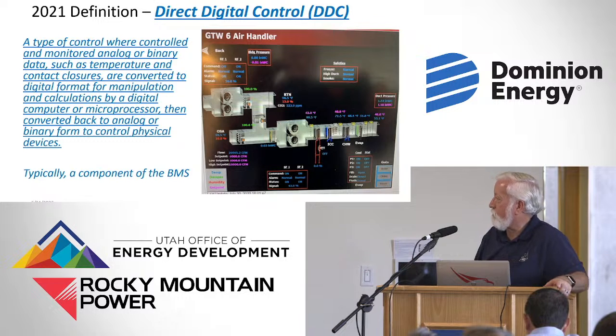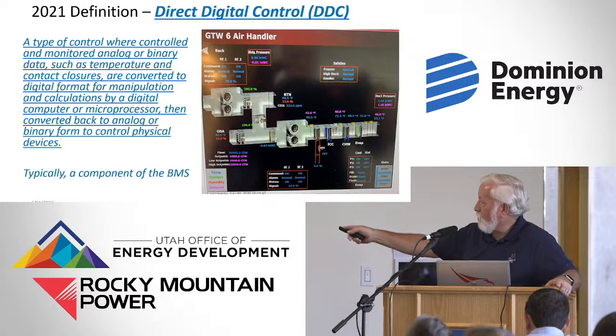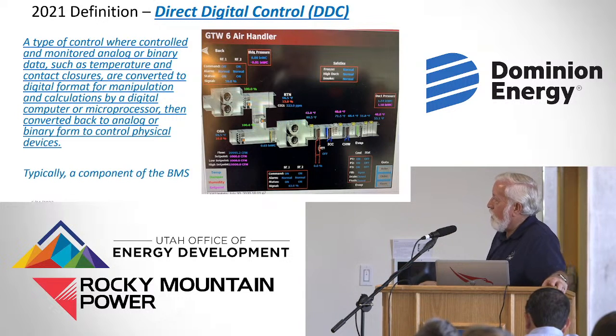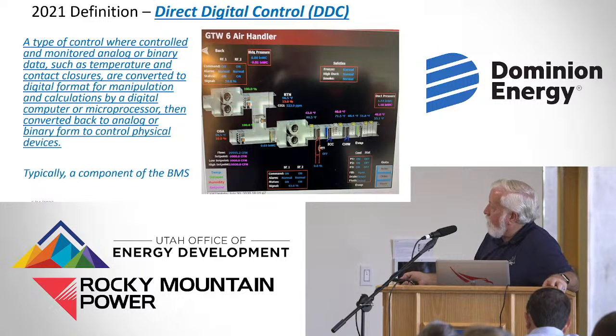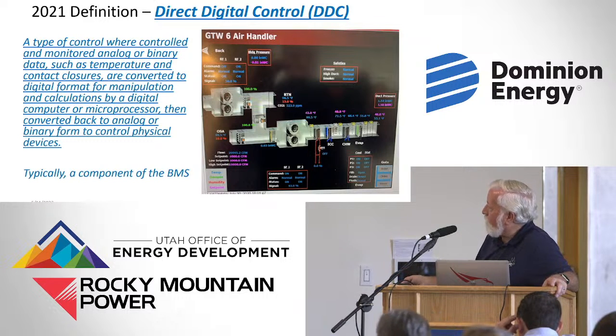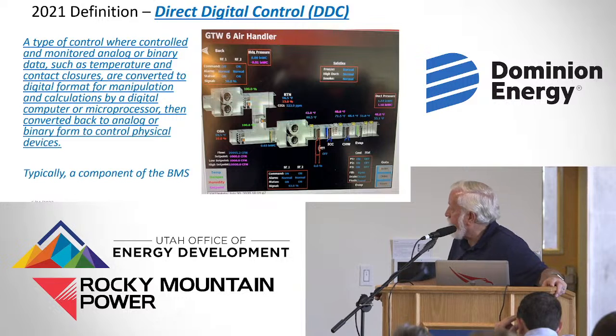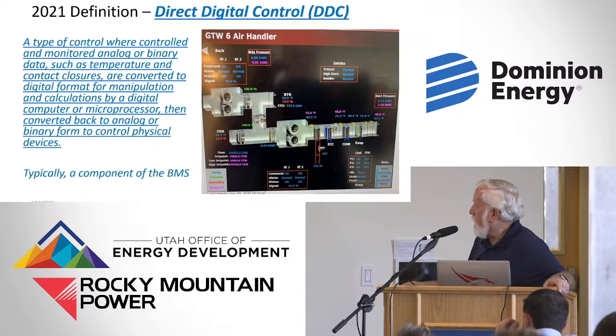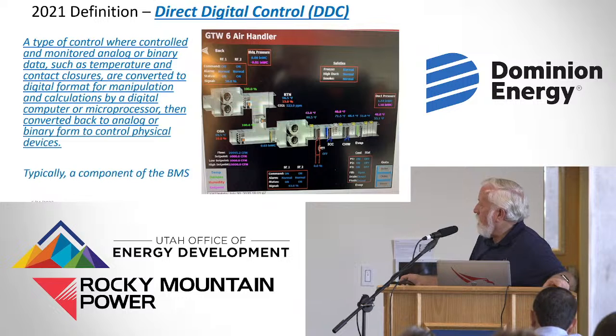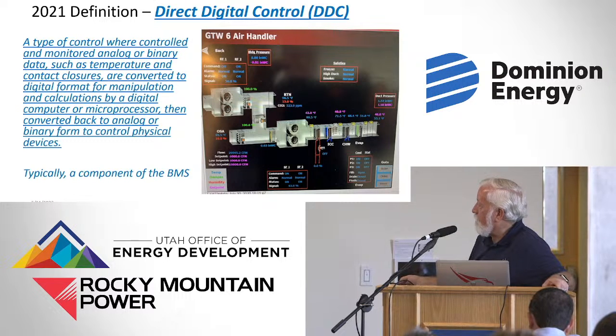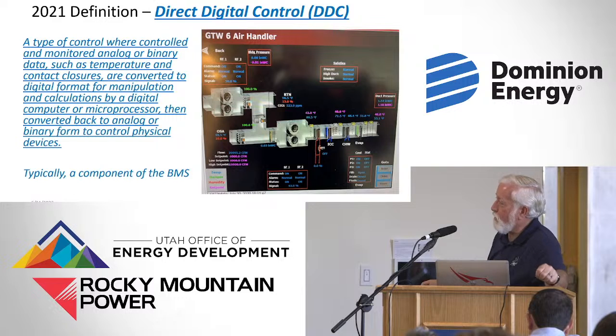BMS is building management system. And this one is an important one I want to point out. Here's our air handler. We're bringing air in from outside. No, we're exhausting air there. We're bringing air in from outside here. Our return path is this way. And we have a heating coil, an indirect cooling coil, a chilled water coil, and an evaporator coil. So we have 4 stages of cooling. We have economizer bringing air from outside if it's cool enough. That'll cool the building.